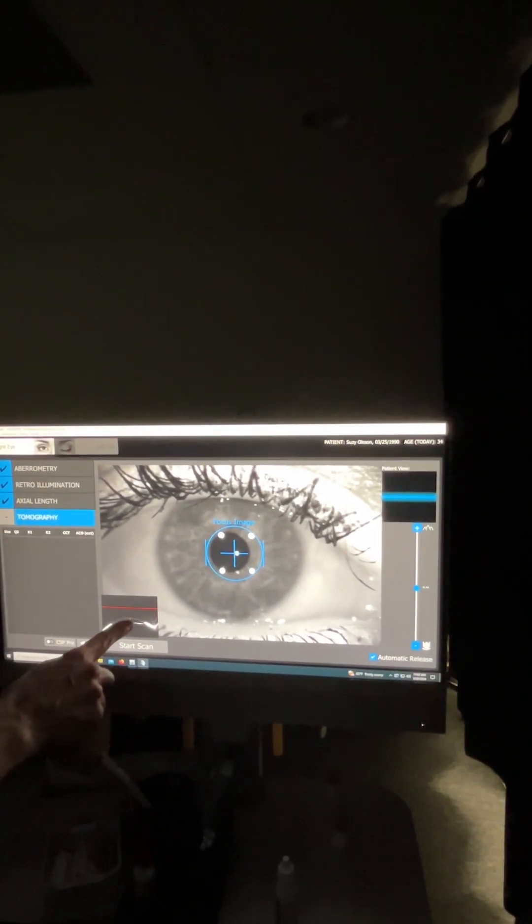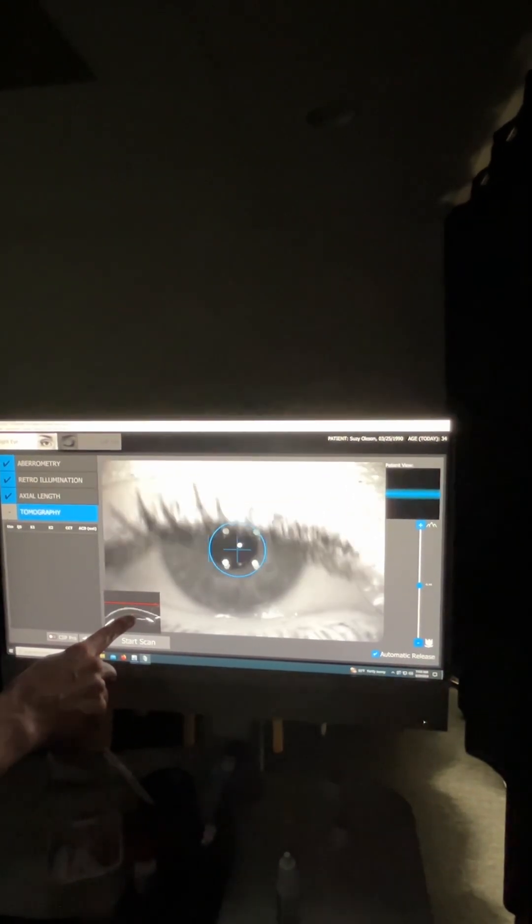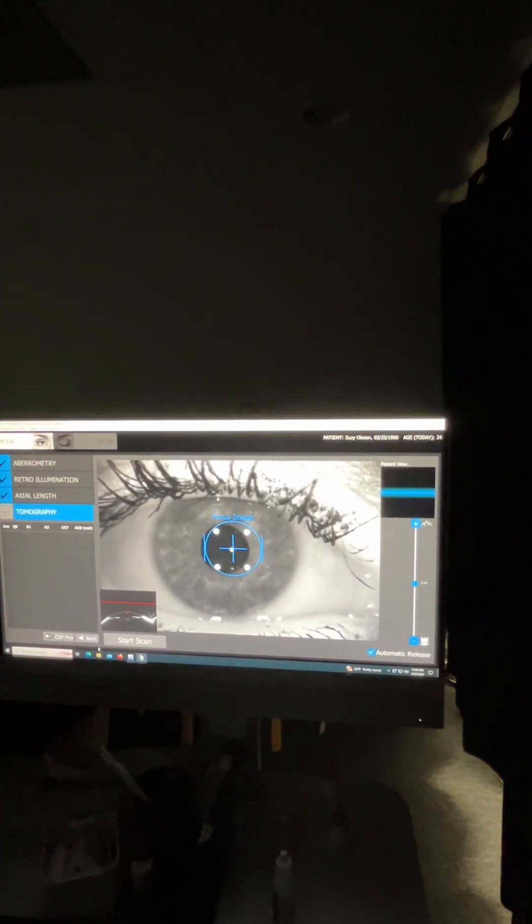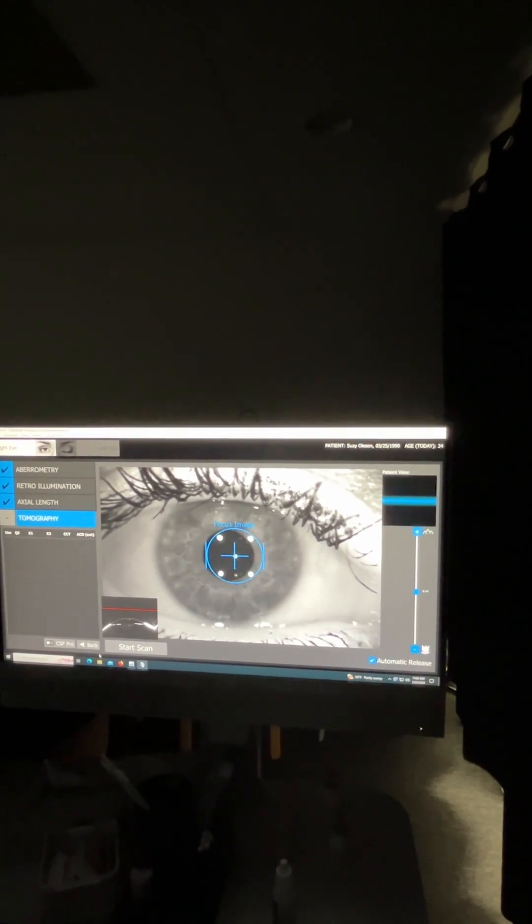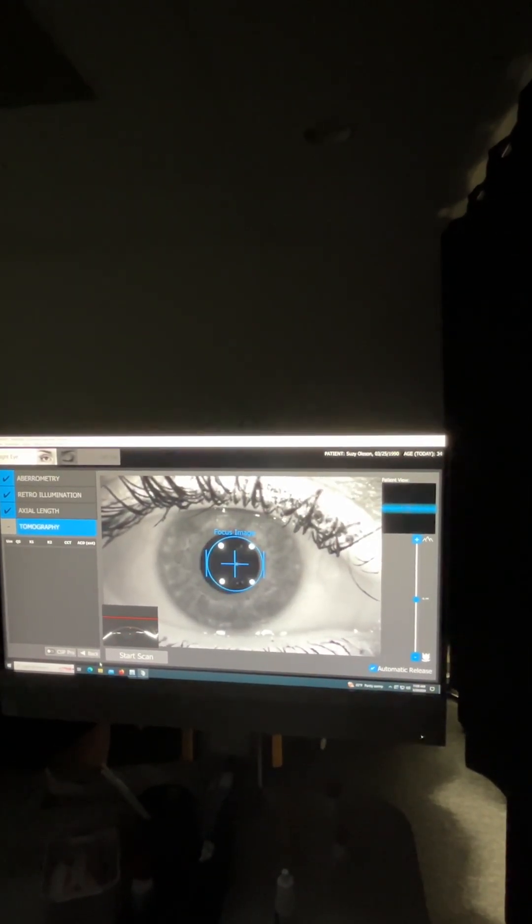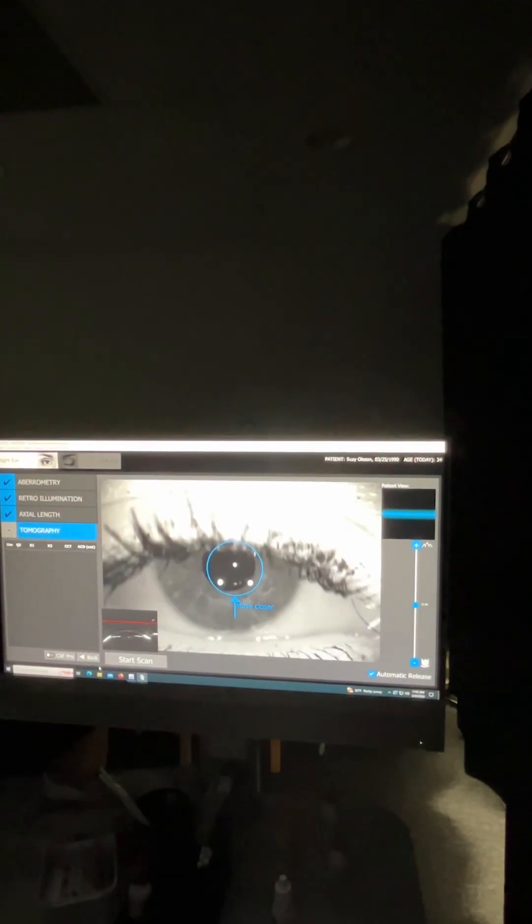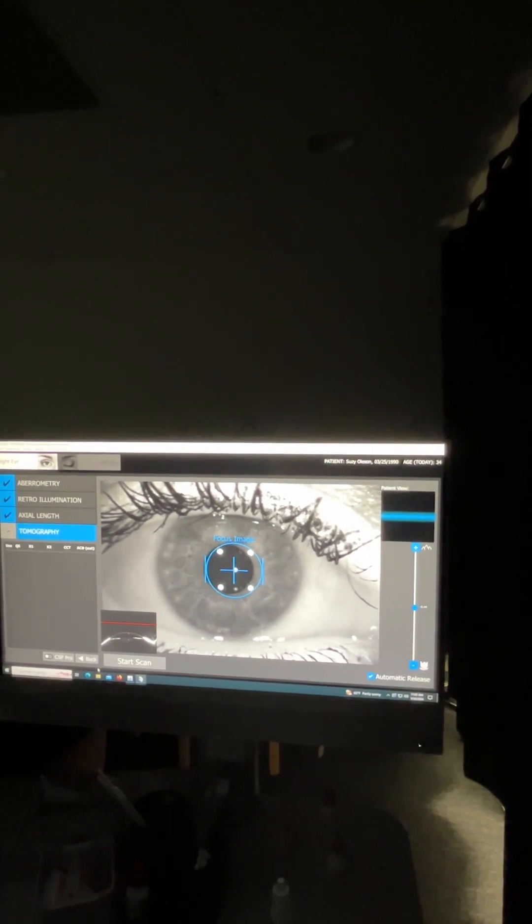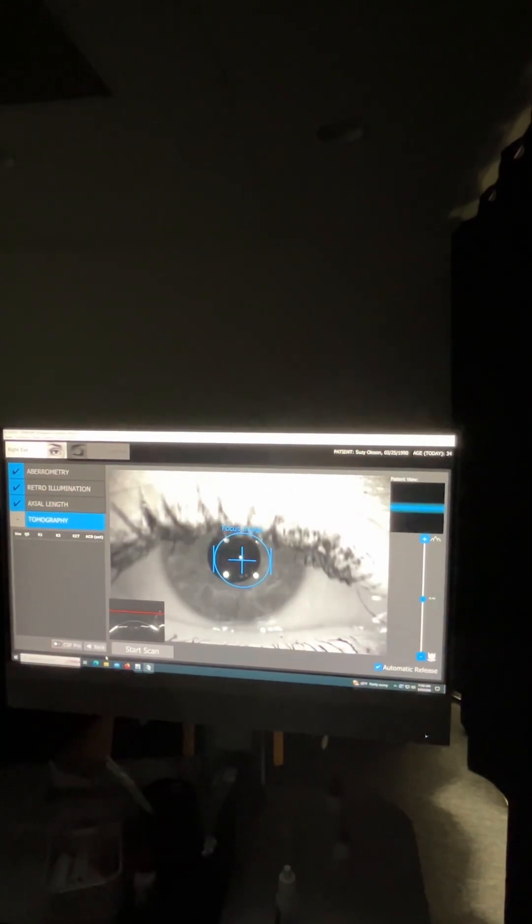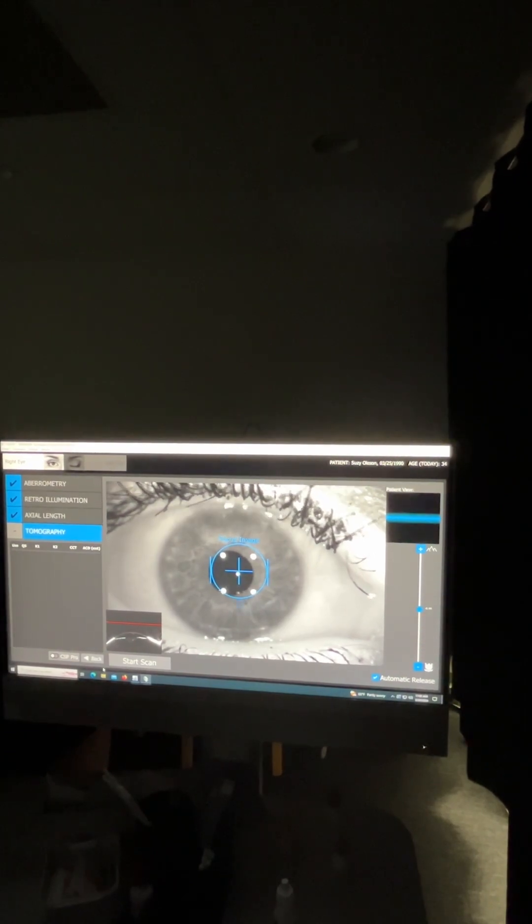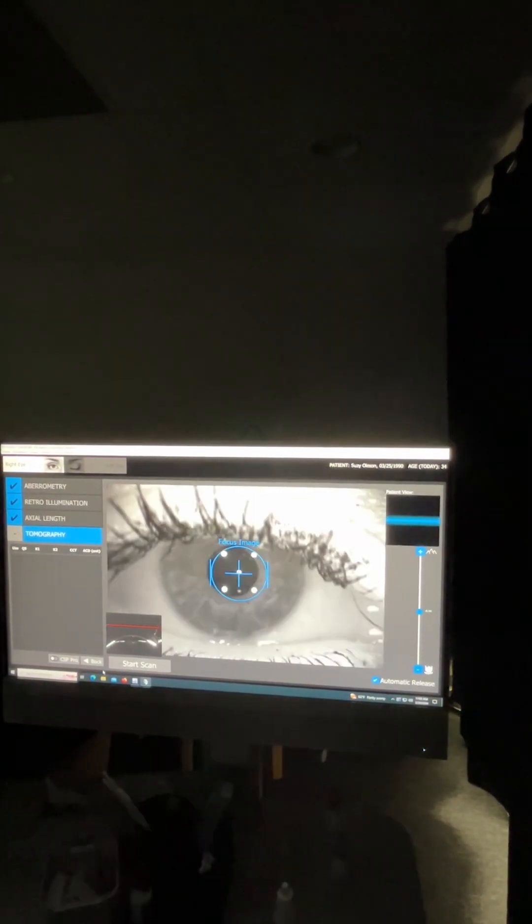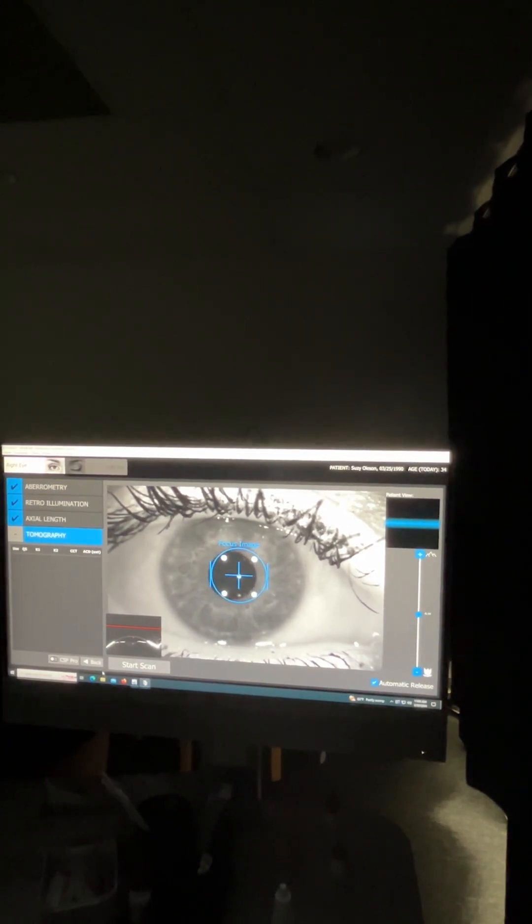Now, if you'll notice in the bottom left of the screen, you can actually see the eye down here and then you'll see that red light or that red dot. When the red dot and the red line touch, that's when the instrument will start capturing. And it's not a single picture. It's going to be about a two second scan. So this is the one that uses the rotating camera and that camera will rotate around 360 degrees. So it's important when you start to get really close where the eye and the line are coming together.